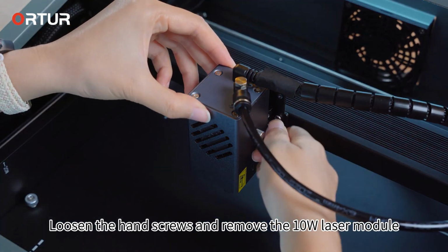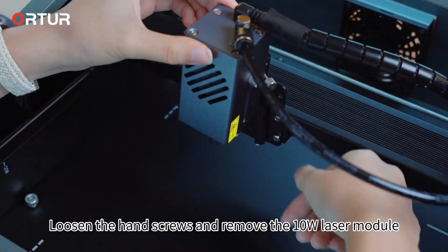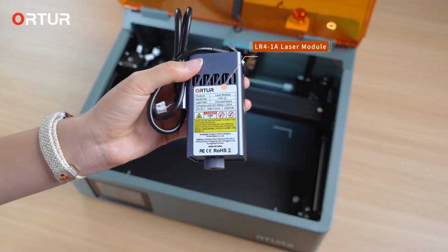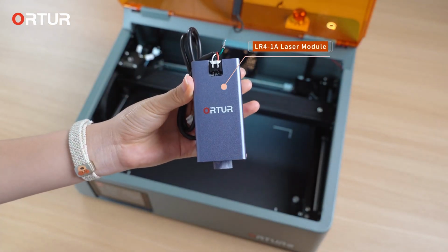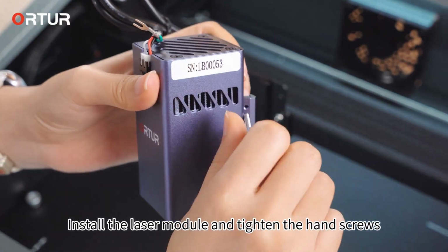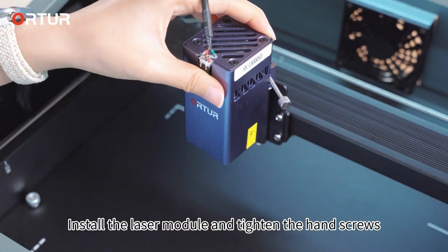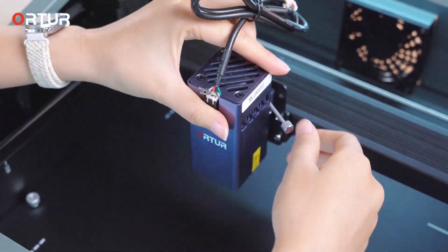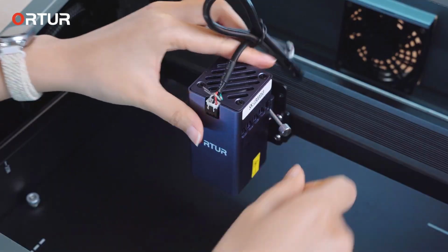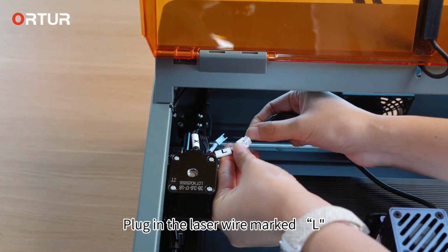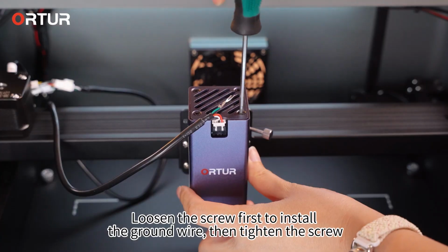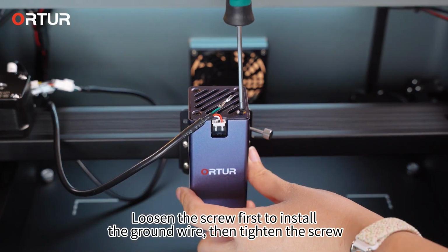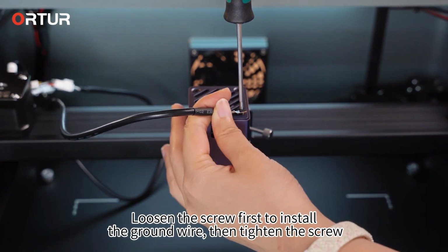Loosen the hand screws and remove the 10-watt laser module. Install the laser module and tighten the hand screws. Plug in the laser wire marked L. Loosen the screw first to install the ground wire, then tighten the screw.